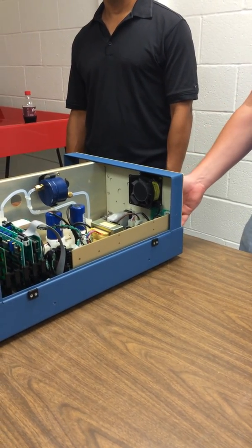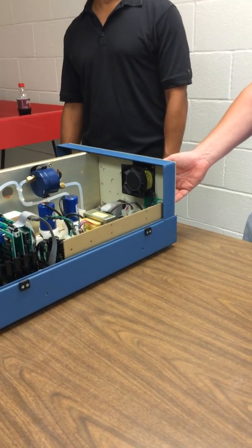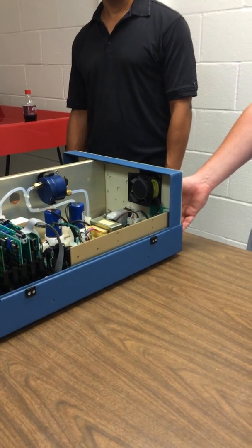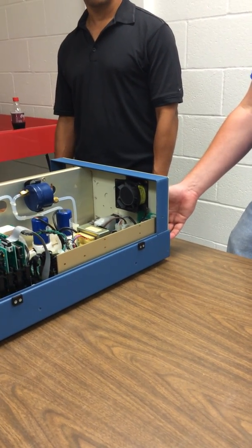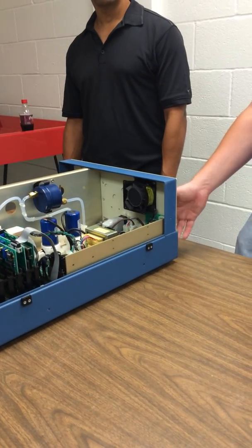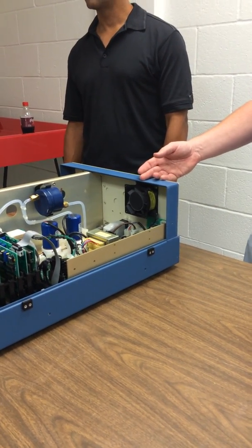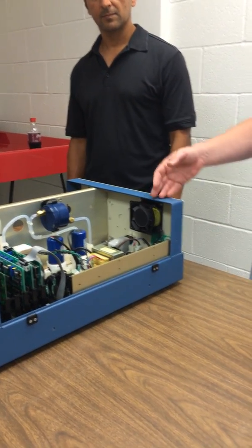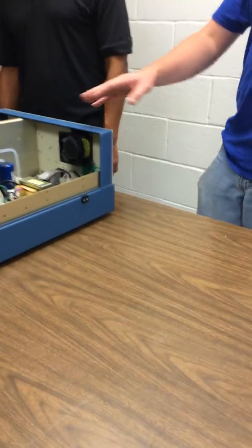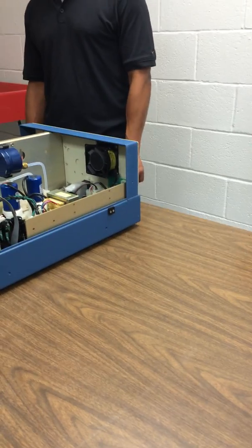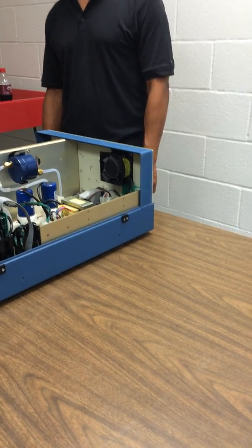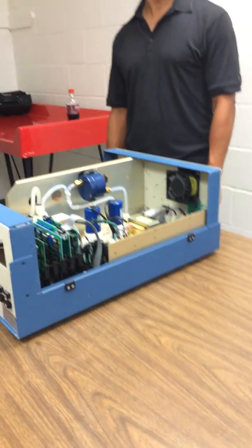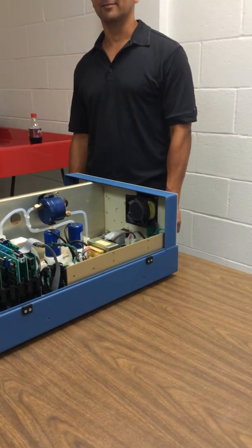Pretty basic. You can either do analog, where you get a 0 to 5 volt output that's proportional to the measurement on the screen, or you can talk to it serially, where you get ASCII text out. That's what we usually do, because that way we can get the rest of the parameters, like Sergio pointed out: the flow sensors, the pressure sensors, things like that. We can read out the internal temperatures. From that, we can leave this in one of our remote sites, log onto the computer, and see pretty much everything about how it's working without actually having to be there. There are most things we can do remotely, but a few things we still have to do.